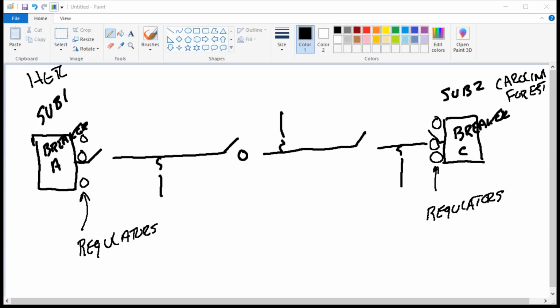I'll let you guys know, not all systems have SCADA. Not all companies have SCADA. So it's good to know these steps. And like I said before, typically you're going to have a line technician A with you that's going to be operating the radio, and you're going to be operating the stick, opening and closing switches. So it's best that you know procedurally that everything has gone correct before you open or close the switch.